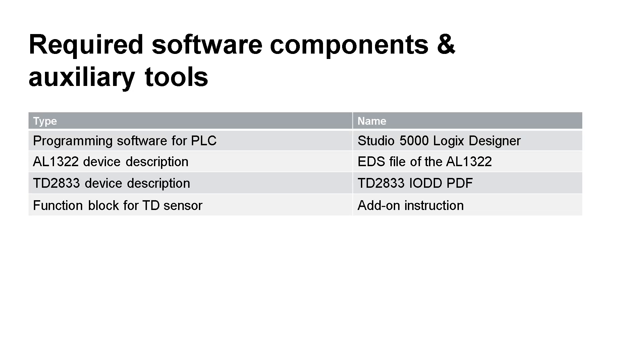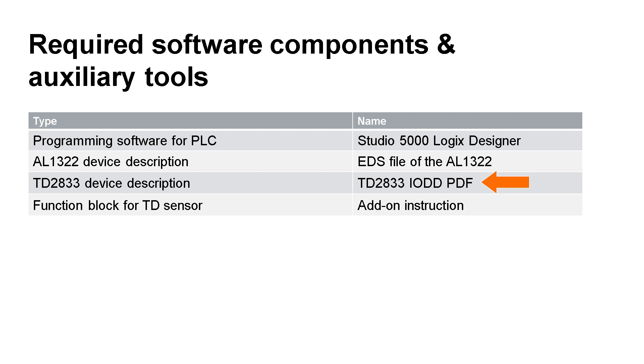Besides the hardware, we also need some software and auxiliary tools to make the whole process work. As mentioned earlier, Studio 5000 is the programming software for Allen-Bradley PLCs. It brings the hardware and the software world together. The EDS file of AL1322 describes the IO-Link master in the PLC. It adds the master to the module catalog in Studio 5000. To read the process data of an IO-Link sensor, IFM supplies add-on instructions in the starter packages. Depending on the device, a function block is provided that shows all of the sensor's process values after configuration. For the calculation of the process value, a gradient is also required, which can vary from one sensor to another. This information can be found in the IO-DD PDF of the temperature sensor used.